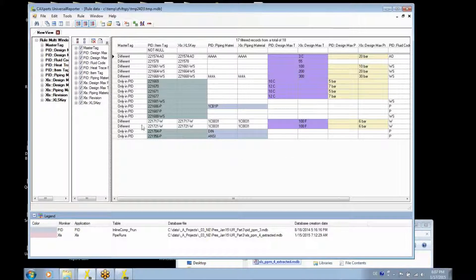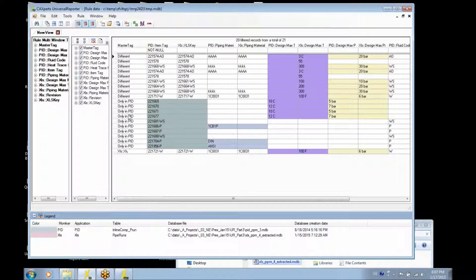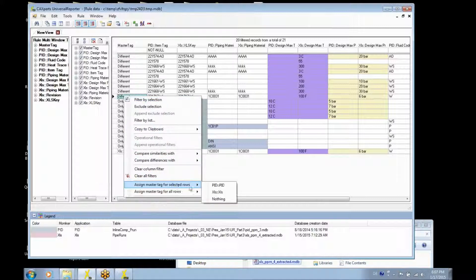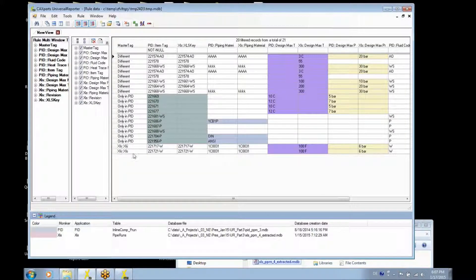There is a function going one step further. For instance, if we want to take values like 6 bar and 100 Fahrenheit and apply them from the Excel values to the PID values, it is possible to select one or more rows and assign the master tag to Excel. Then there are two rows where Excel is assigned as a master tag, and an update function in Universal Reporter will update the Excel values into the PID window.